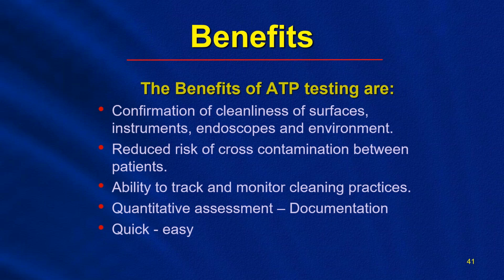If you have the Joint Commission come in and they want to know how you are testing for cleanliness, you can generate and run reports from this program to show them what you're tracking and the results of the tracking. But the main thing with ATP testing, it's a quick and easy test. You get results in as little as 15 seconds. So it's a quick and easy way to determine if your instruments have been cleaned properly, an effective cleaning.